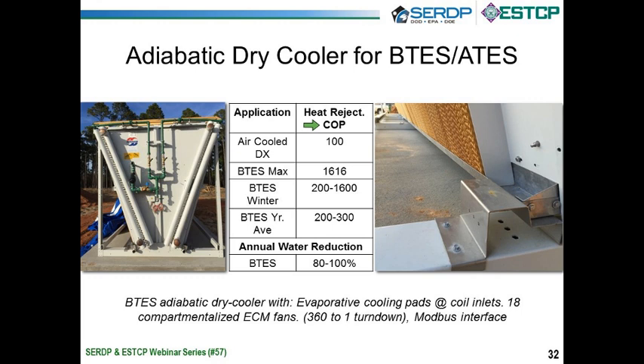Typically, your air conditioning unit sitting outside your house, a heat pump, cooling only, 4 tons, you're going to have to spend about a kilowatt hour to dump 100 into the atmosphere in the summertime, 95 degrees outside. With these systems running in the wintertime and the cold air and slowing the fans way down, we could hit as high as a COP of 1600, but that's not normal. Over the course of a winter, we're basically telling you that we can dump the heat 2 to 3 times more efficiently than you could in the summer when it was really hot. This doesn't have anything to do with the compressor or the overall COP. This is really just referring to the COP of heat rejection.